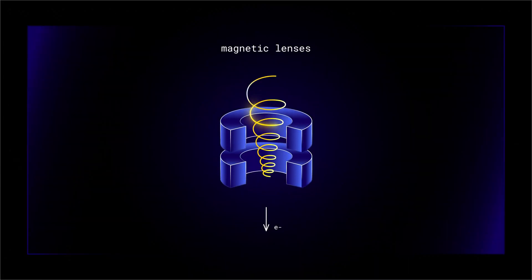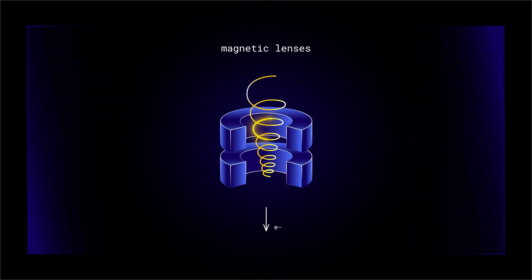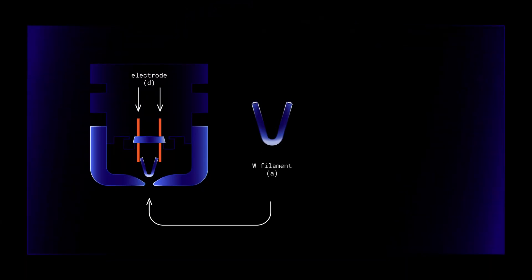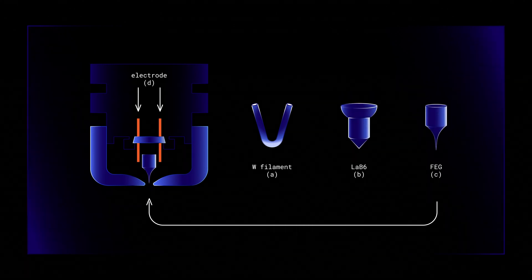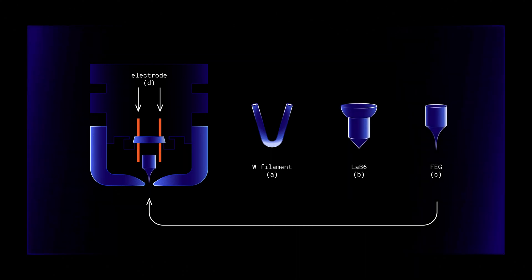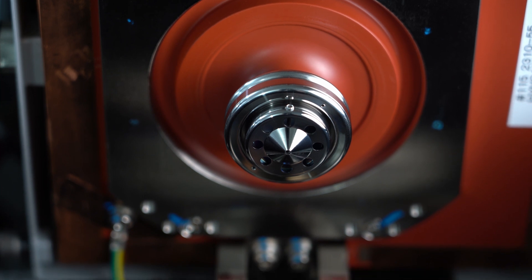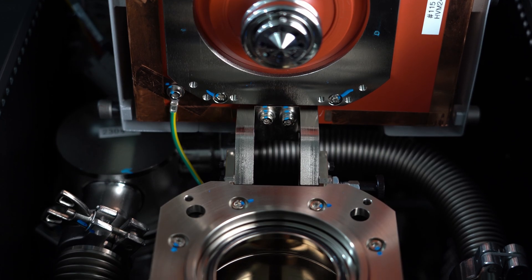Magnetic lenses create a magnetic field that allows you to control the beam shape, astigmatism and focus. The emitter can be tungsten wire, crystal of lanthanum hexaboride, or a special sharp crystal of tungsten in field emission guns. In our case we have tungsten hairpin filament with thermal emission.